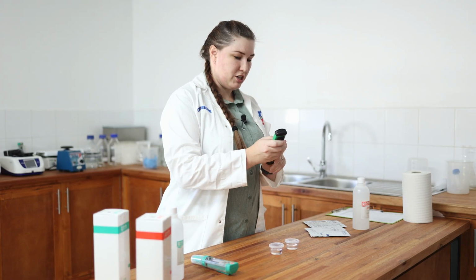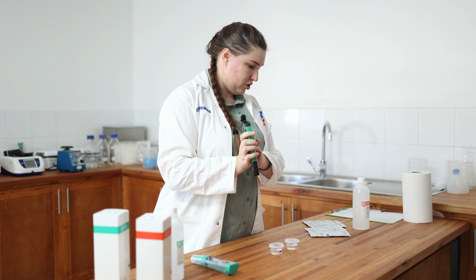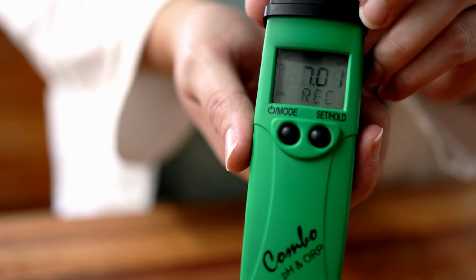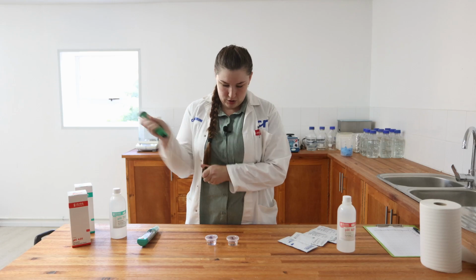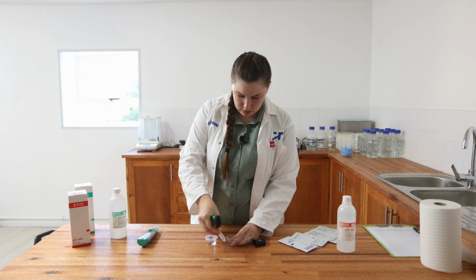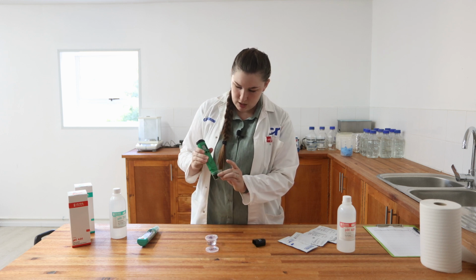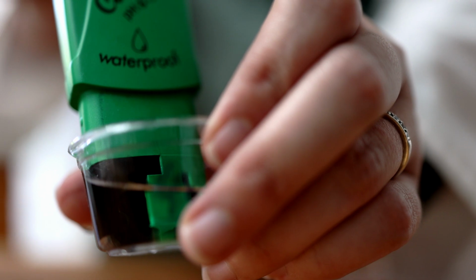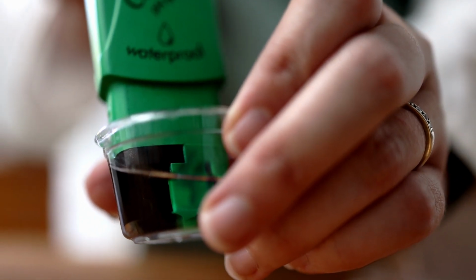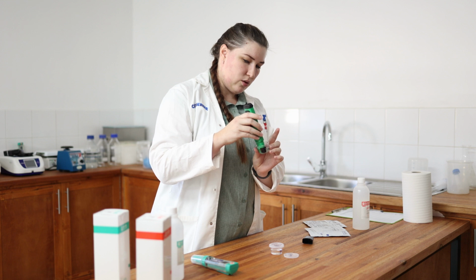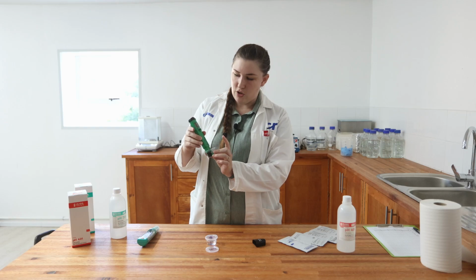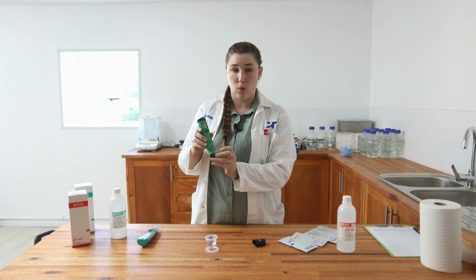So back to the calibration. You've got it already switched on. So in this pH meter, you would hold down the on and off button. As you hold it, there'll be a small little word there that says CAL, C-A-L for calibration. Immediately, it's telling us 701, record. So you take the meter and you open up your pH 7 buffer and you submerge the electrode. Make sure that the electrode is submerged so you have enough solution. You just want to hold it in there, move it around if you need to, and you wait. Sometimes this can take quite a while.